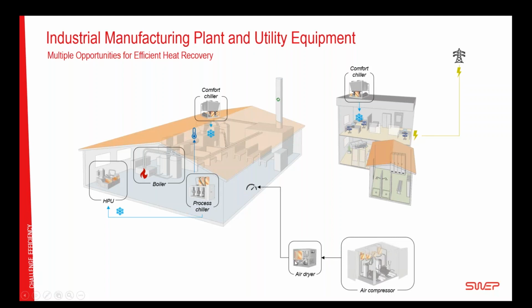We can find the brazed plate inside the air dryer machine, where it cools, dehumidifies, and reheats the air. We have them as an evaporator and condenser in the process chiller. We can see them as an oil cooler in the HPU. So already now there are a lot of places where a brazed plate is used for everyday industrial and HVAC operations.